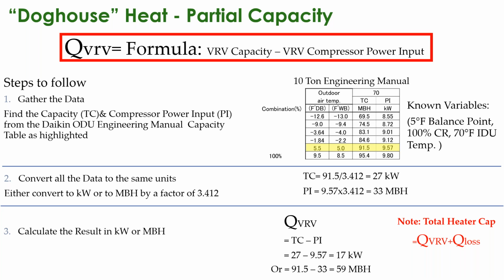The variable refrigerant load is going to be your total capacity minus the power input. So if you were looking at it in kW, that would be 27 kW minus 9.57 power input, leaving you with 17 kW that you need to make up to maintain that balance point. Or if you did it in BTUs, 91,500 minus 33,000, you'd need 59,000 BTUs to maintain that balance point.